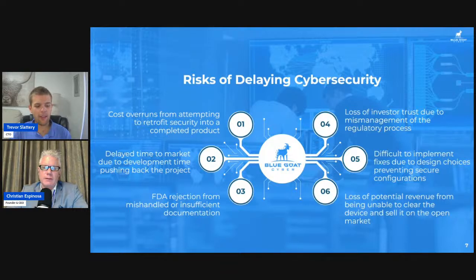If we identify that we can't fix something outside of a design freeze without a new round of verification and validation testing, the whole timeline is going to get pushed back, since we're going to need to redo software documentation on top of cybersecurity documentation.